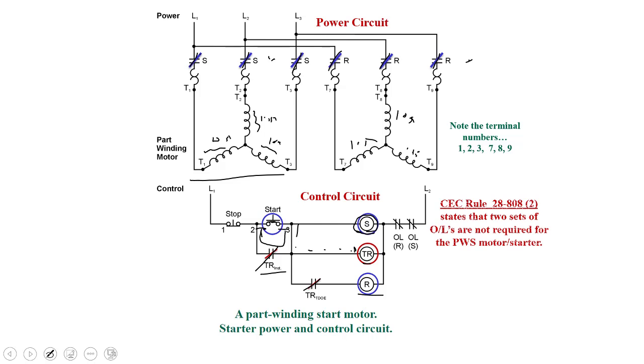So, going through how it starts and runs. Notice that we've got several overloads drawn here. There's a code rule regarding that. It states that two sets of overloads are not required for part winding start motors, PWS, but often you will see two sets of overloads.